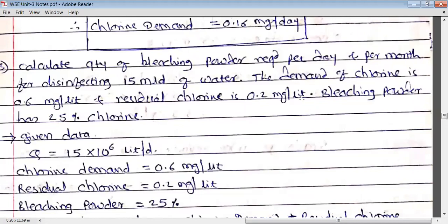15 MLD — MLD stands for million liters per day, where million means 10 to the power 6. The demand of chlorine is 0.6 mg per liter, and the residual chlorine is 0.2 mg per liter. Bleaching powder has 25% chlorine.